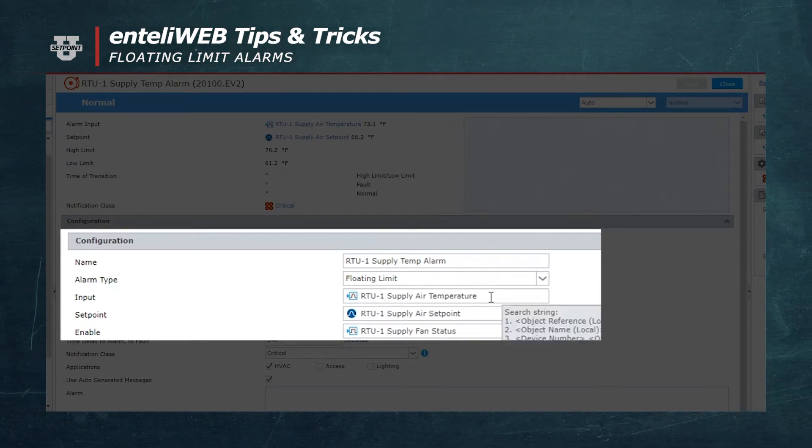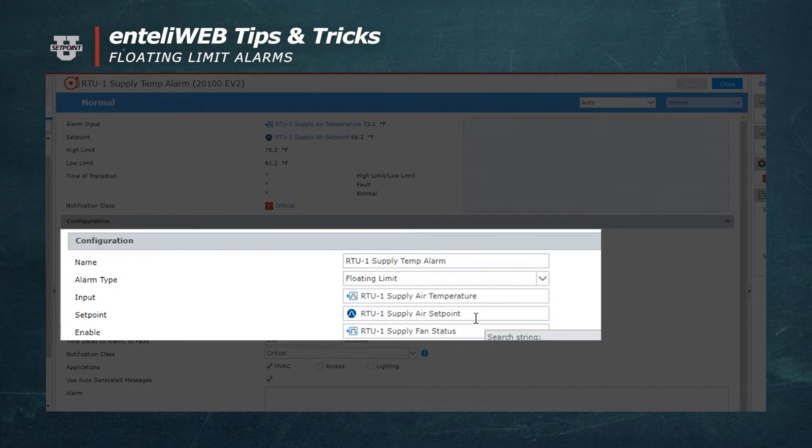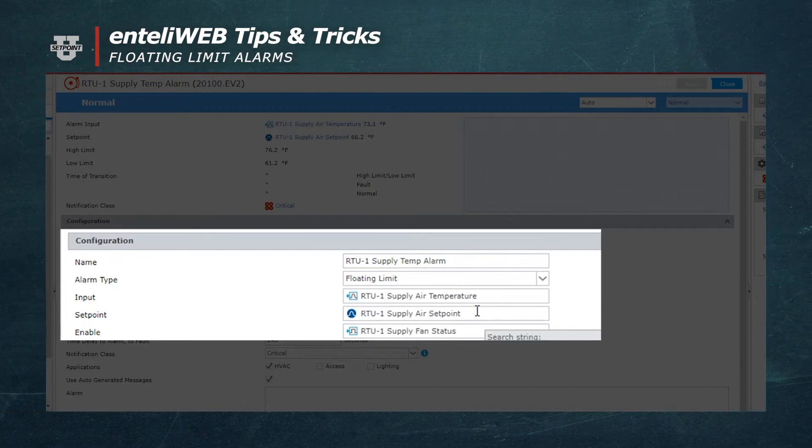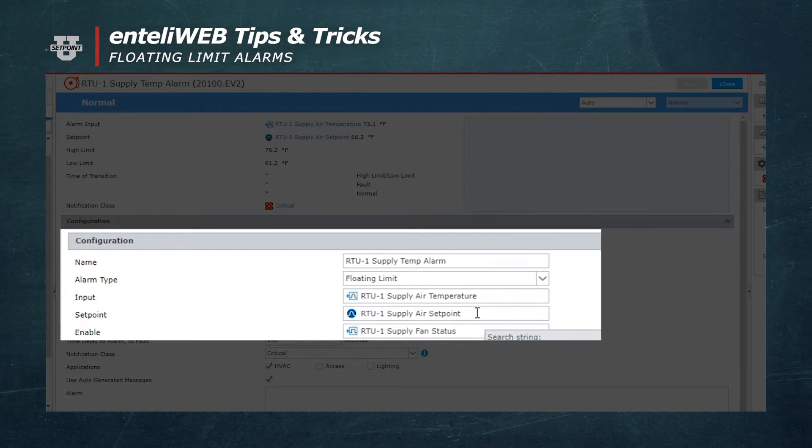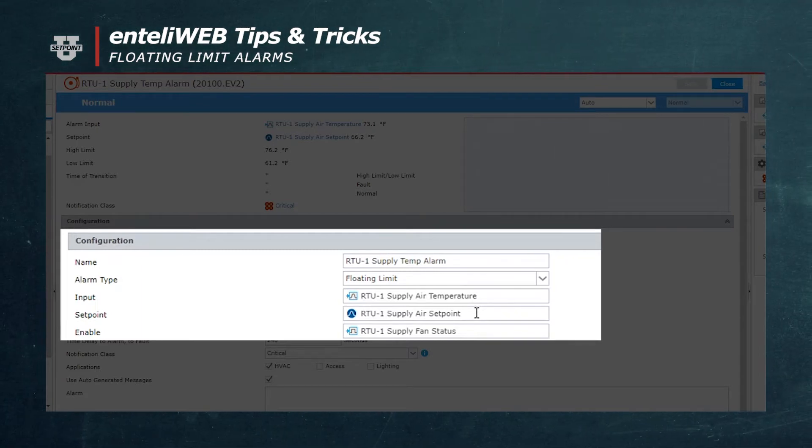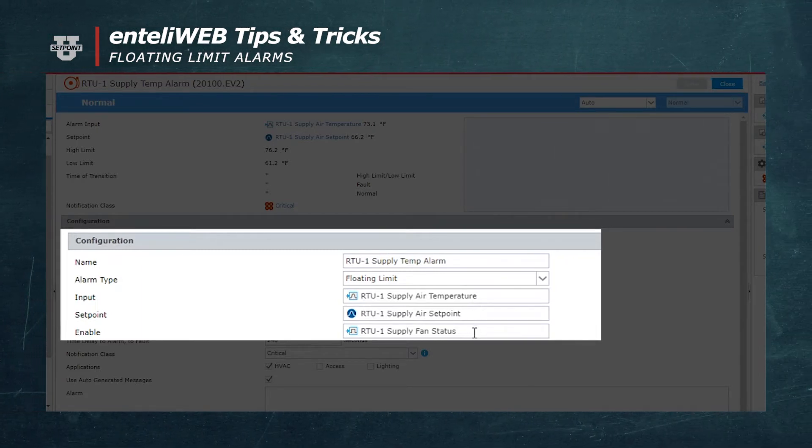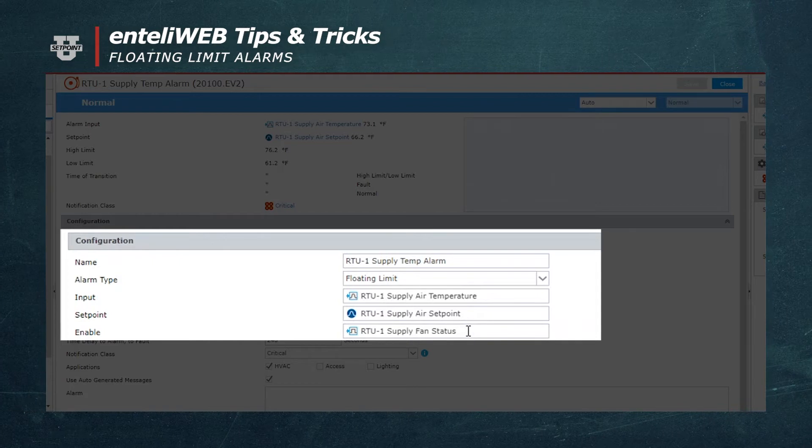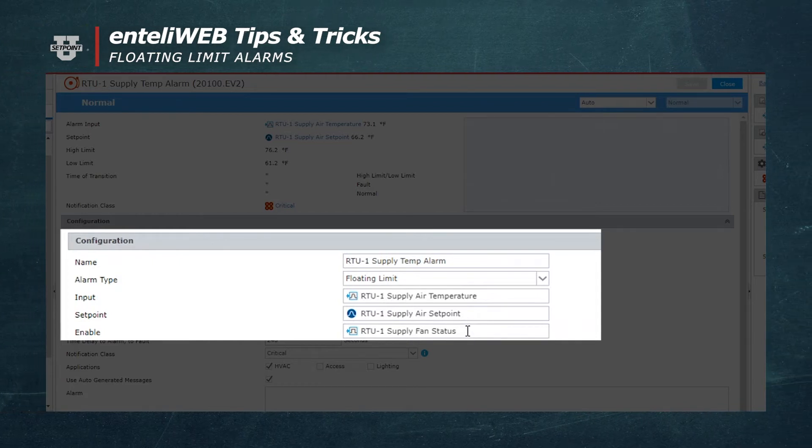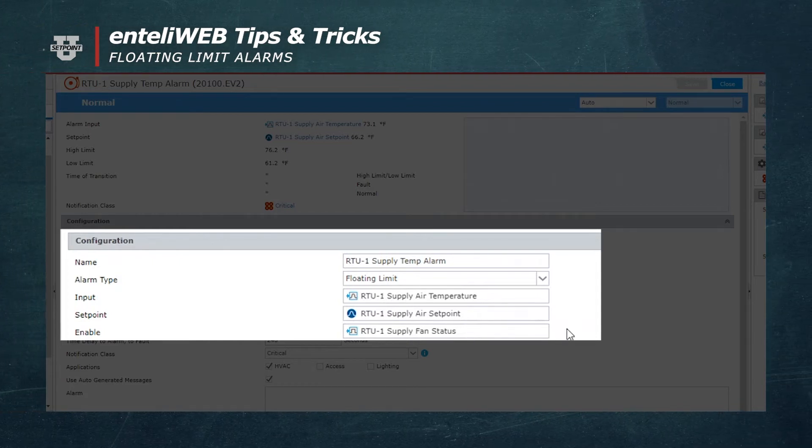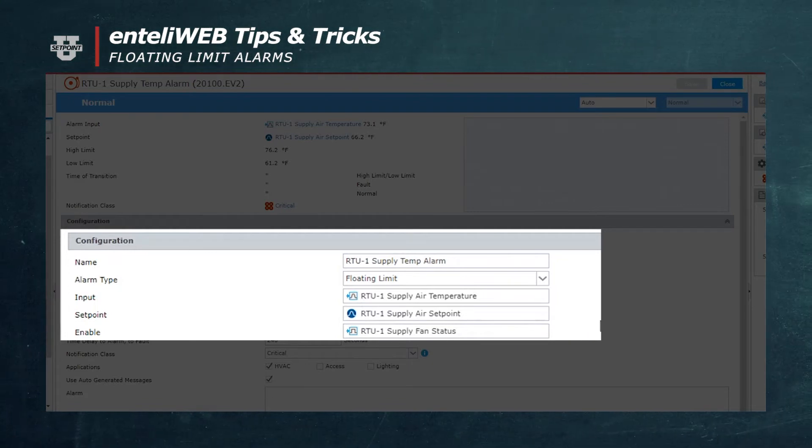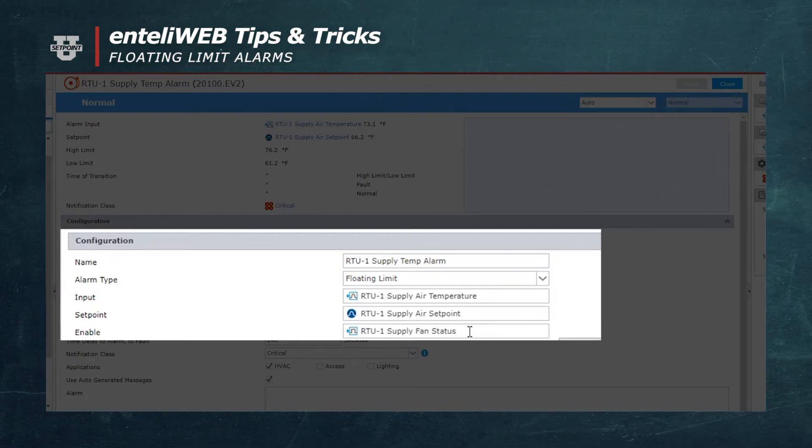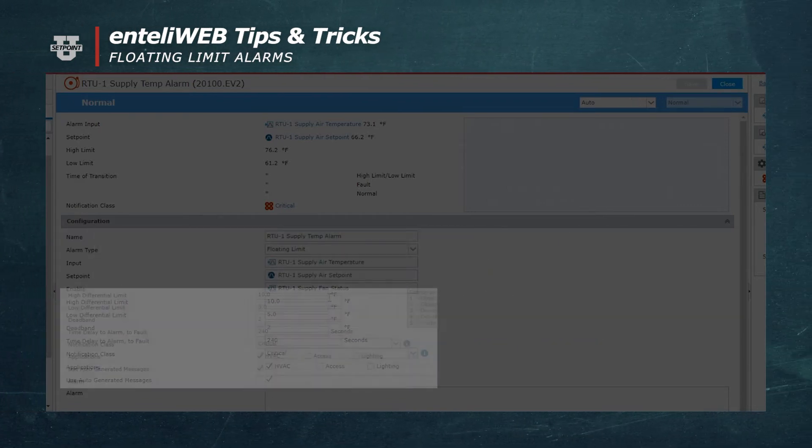It's got the supply air temperature, which is the temperature we want an alarm. It's got the supply air setpoint, which is presently set at 66 degrees, and it has the status of the fan. So the status of the fan in this case is used to enable the alarm. As long as the status is on, the alarm is functional.